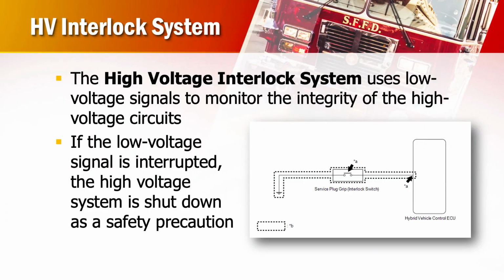I've got an interlock system. What it does is make sure everything's connected. It runs low voltage through the entire system telling the computer all the cables and connectors are plugged in and everything's functional. Once it sees the interlocks are complete, it turns the high voltage system on. If it's interrupted at all, if I open up the interlock, it turns off the high voltage. That's one way we can disable the high voltage, by opening the interlock.